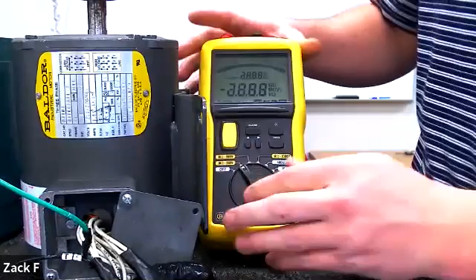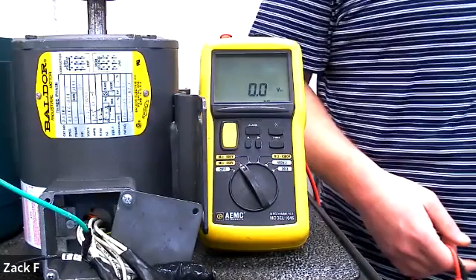That really depends on what you're working with. It's best to start with the lowest setting. In this case, it's 250 volts. For your labs, you won't need to go higher than 250 volts. Running it at higher voltage, if you continually run a Megger test at a higher voltage, you'll eventually start to break down the insulation of that system.